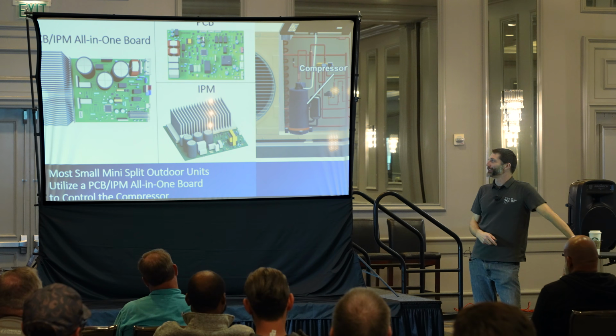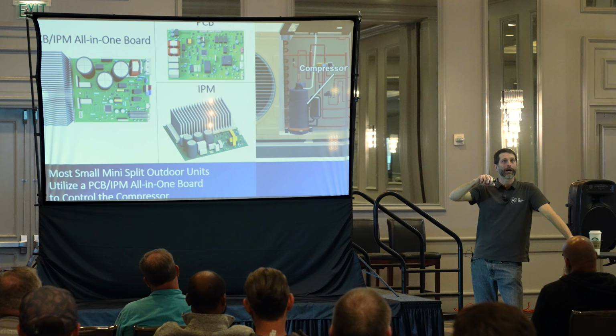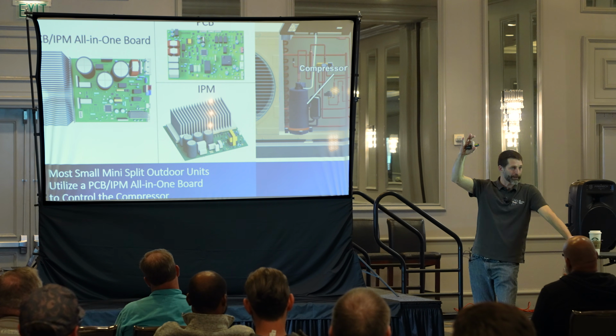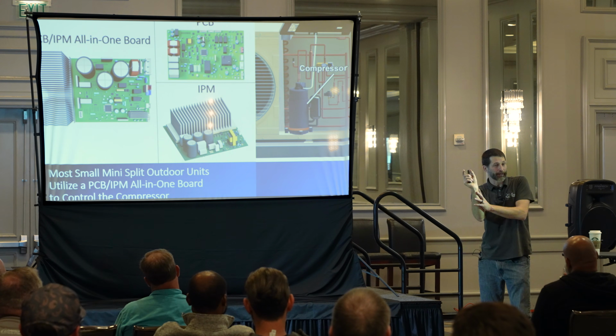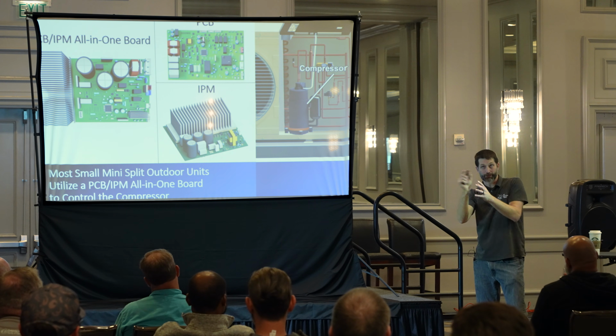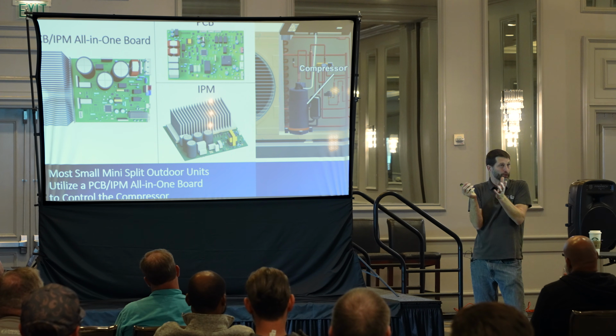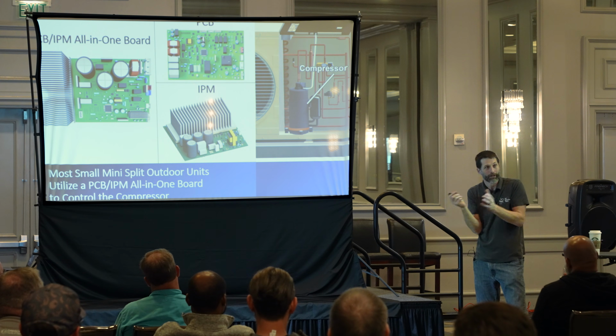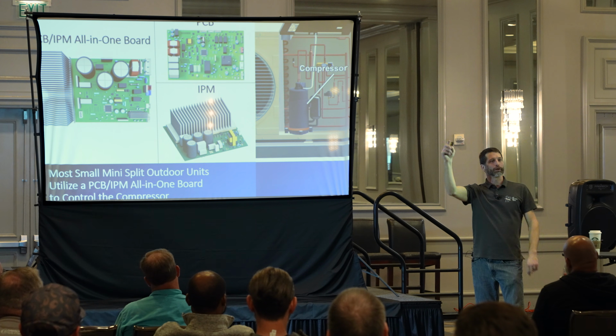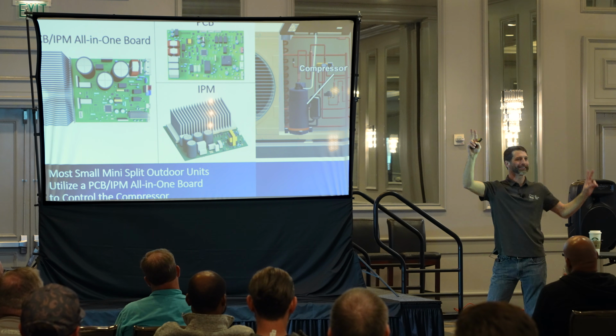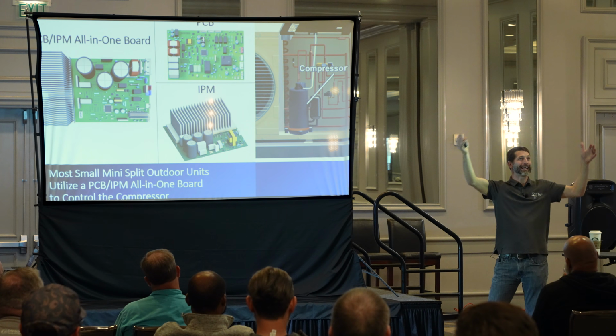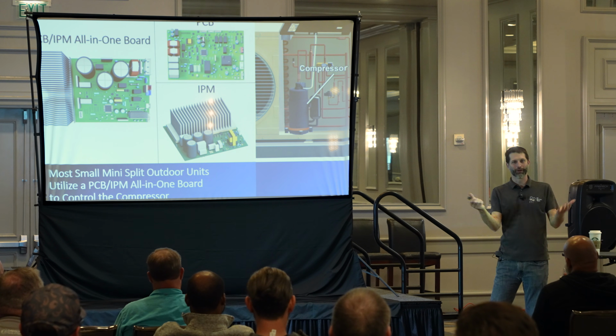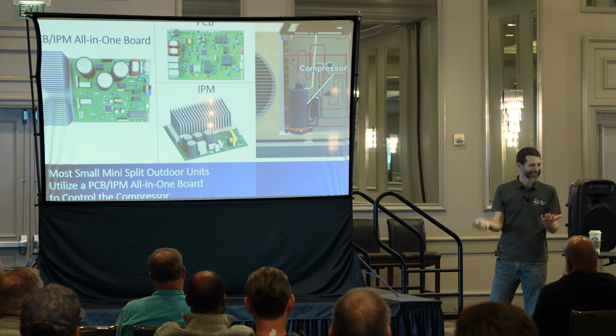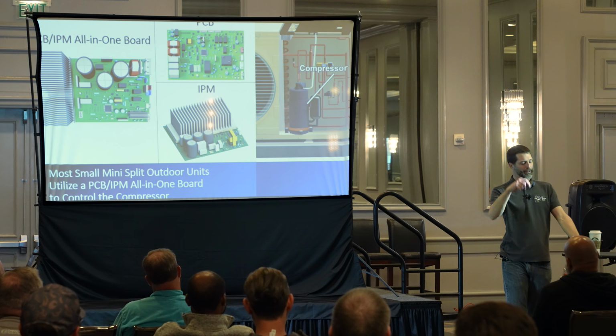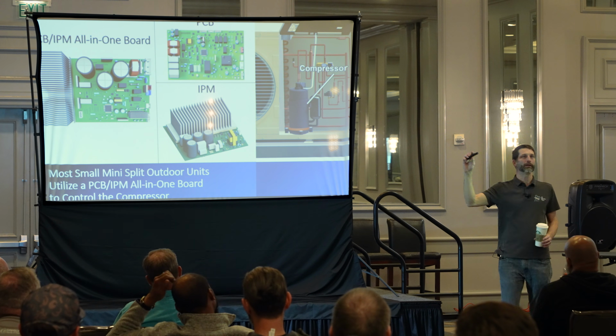They also have disconnect boxes that have the surge protection built inside of it, with an LED light that tells you if it's working. If not, the protection device is no longer protecting the system. The problem is, if you're a licensed HVAC contractor, in many states you're technically not allowed to switch out the disconnect. So what are we supposed to do there? But anyway, yes, surge protection, absolutely 100%.